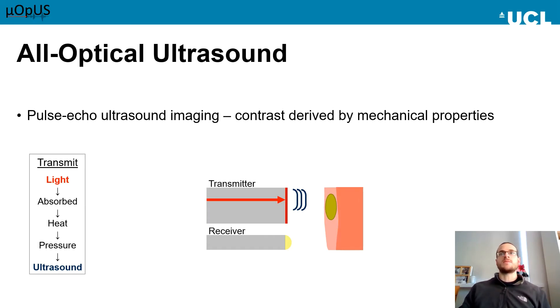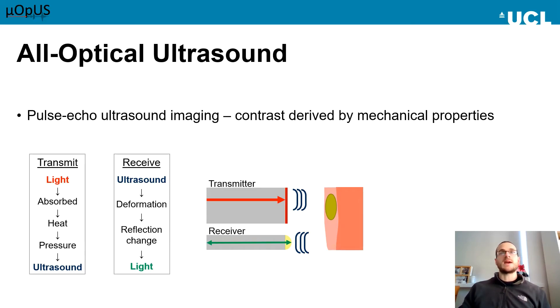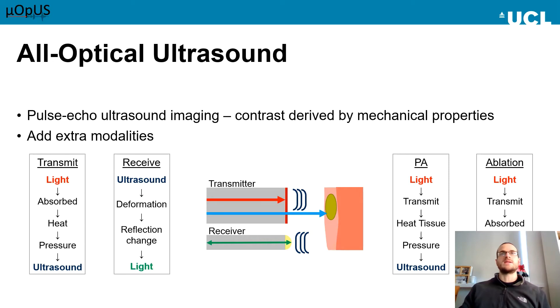The reflected ultrasound signal can be detected interferometrically, in my case using a fibre-optic Fabry-Perot interferometer. Ultrasound impinging on the sensor causes deformations, which modulate the light reflected from the device. This reflection can then be monitored to give the ultrasound signal. One advantage of optical ultrasound that I'm particularly interested in is the ability to incorporate complementary modalities, such as photoacoustic imaging or laser ablation, using the optical fibres that we already have in place.